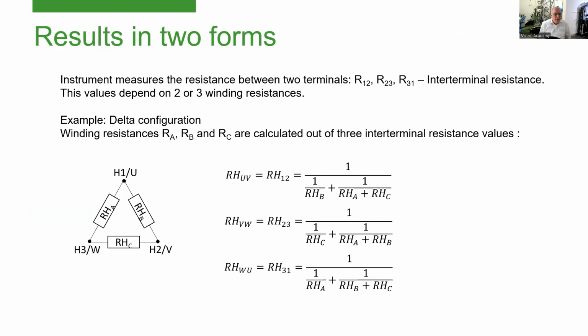So what is something new or special in this instrument compared to its younger brother, the digital transformer analyzer? With the winding resistance analyzer, we get the results in two different forms. You must know that basically the winding resistance meter always measures the resistance between two transformer terminals. You know that we have different configurations, delta or star configuration. If you measure the resistance between, let's say, the H1 and H2 terminals, the measured resistance is always a combination of three winding resistances, A, B, and C. Here are the formulas for the relation between what is measured between terminals and the actual values of the windings.